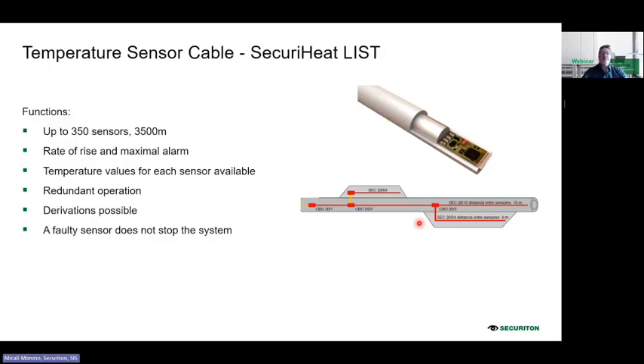Then, a faulty sensor does not stop the system. This is also important to know. If a sensor gets damaged, it could be that the cable was cut, or there was an accident, and during the accident maybe a few meters of cable were damaged. That means that not all of the system will stop. We isolate the few sensors that were damaged, but the rest of the sensors are working properly.